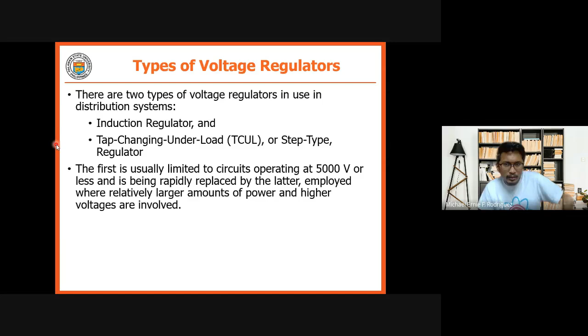The induction regulator is not commonly used anymore because it is limited to 5,000 volts or below, so it's not suitable for our system now which is at 7,620 volts line to neutral. Nowadays, what we use is the step type regulator.